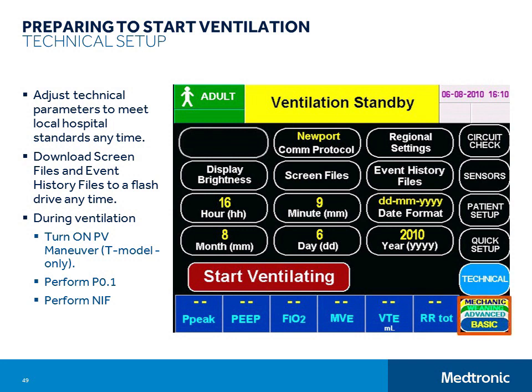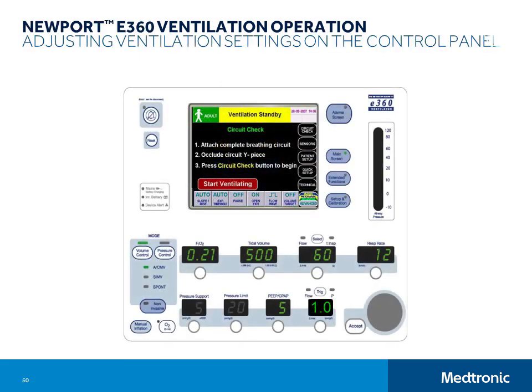Volume control and pressure control breath type activator buttons are located on the control panel, and volume target pressure control and biphasic pressure release are activated using touch controls in the advanced data set on the graphical user interface. E360 ventilator controls are adjusted using the touch turn accept method I described earlier, but a couple of controls function a little differently. The trigger control is used to adjust either flow triggering or pressure triggering.